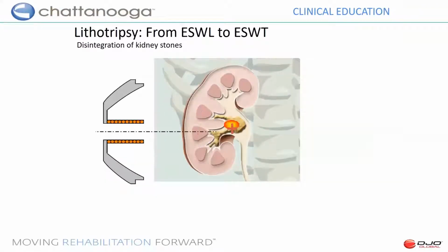So acoustic wave therapy includes radial pressure wave, pulse wave, a few different names for it, and shock wave or extracorporeal shock wave therapy. It stems from lithotripsy. Lithotripsy is an acoustic energy that's designed to travel through the tissue, and the way it's designed in its electromagnetic coil, it's a parabolic design, so it emits energy from different areas at lower concentration, but they converge to hit a target at a depth below the skin surface.